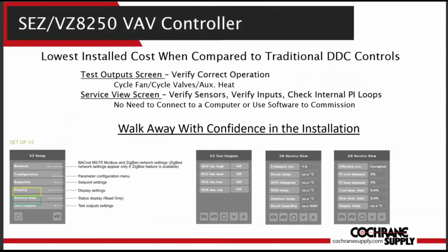The test outputs and service view screens are great ways to verify the installation is performed correctly. Service view provides values of the attached sensors, the outputs from the heating and cooling proportional integral loops, and if there's any alarms, like an open window, dirty filter, or general service. Basically, a way to view what's going on inside the controller without the use of a computer or commissioning software.